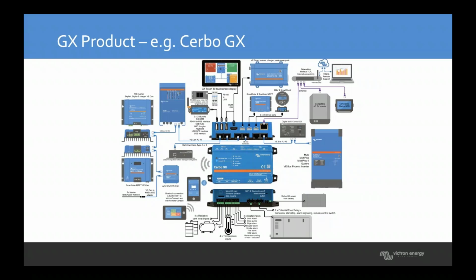There's a lot of features that come with this, and it's a highly recommended feature to have, but it is not essential. In an off-grid system, our MultiPlus units can frequency-shift power, controlling an AC PV Fronius inverter without a Cerbo GX or any other GX device. A GX device is required if you're going to have an ESS system, where the system is connected to the grid and the Victron system adjusts the power in real time to make efficient, optimum use of that grid system. That's when they're required, but in off-grid, they're not - though still highly recommended.